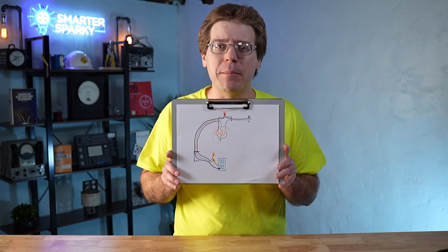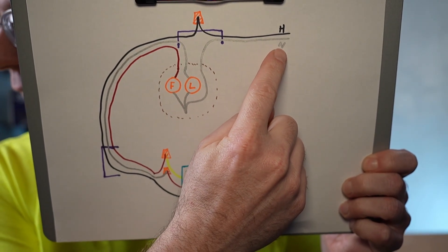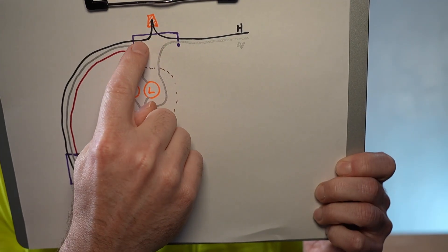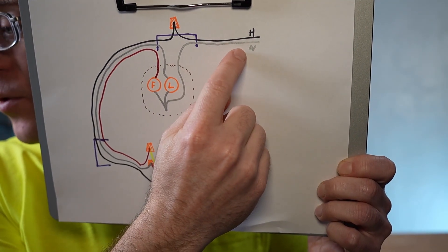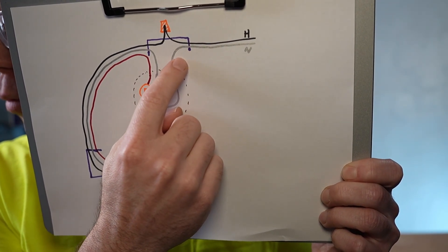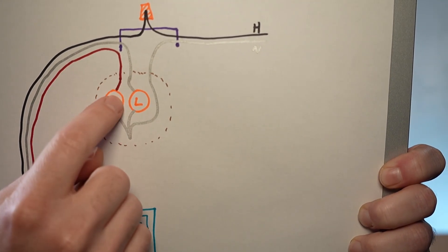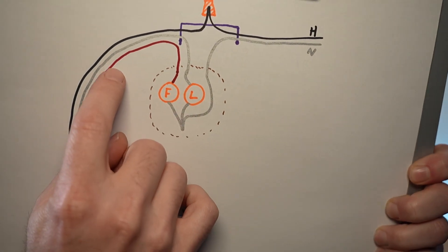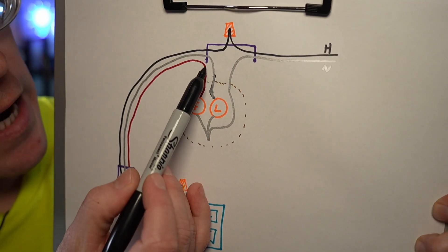So this diagram right here is actually the corrected diagram. So you're going to see in live here in the video as I continue playing this, that I connect the yellow wire to the white wire that I re-identify with that black tape. We're going to actually need to take the switch apart later and flop the yellow and the red around. No big deal. And we're actually going to see what happens when that occurs. But that might be a situation you might run into in the real world. Colors don't match and we have to correct it on the fly. So let's take a look at this diagram and see why isn't there a neutral at that switch. Basically what's happening is they actually bring the home run all the way up to the box up in the ceiling. So this purple, let's imagine that's the box up in the ceiling for the fan.